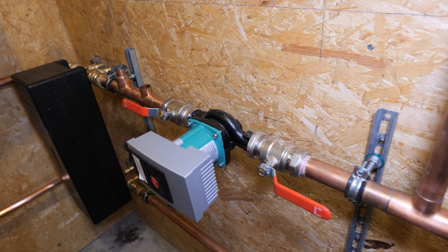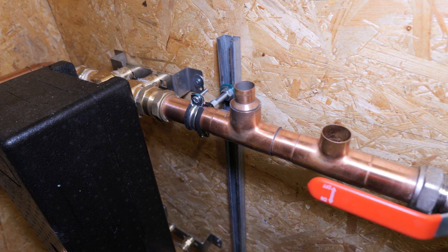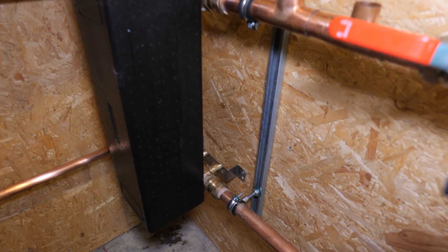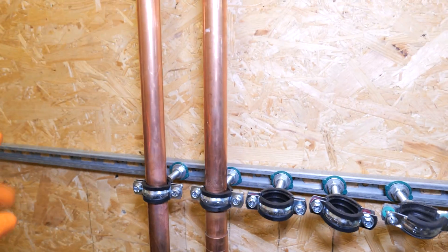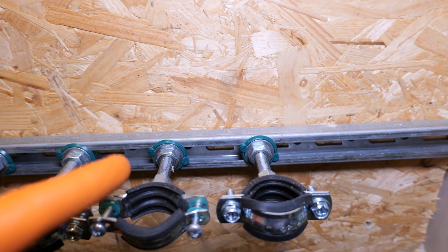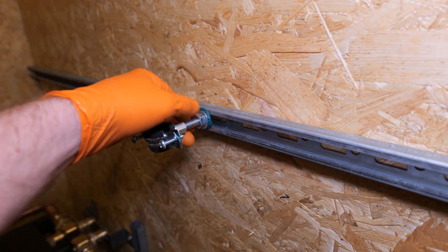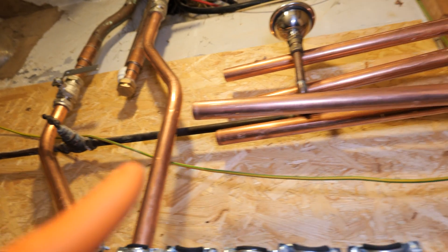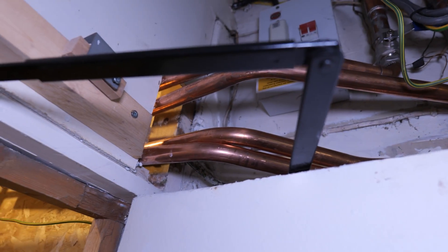We solder all these connections — in any plant room you can access, you should really be soldering. Press fitting is great in kitchen cupboards and lofts, but anywhere accessible you want to be soldering. We've got Unistrut on the wall — this is by Walraven, I think it's called Rapid Rail — with Euro clips that just quarter-turn, twist and lock in. I've started getting some of the pipework through pulling them into the boiler room, looks a bit messy at the moment as we haven't got them in position yet.